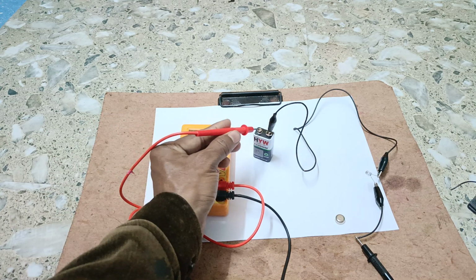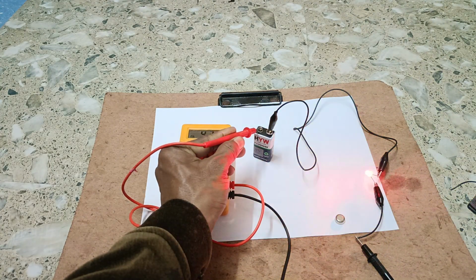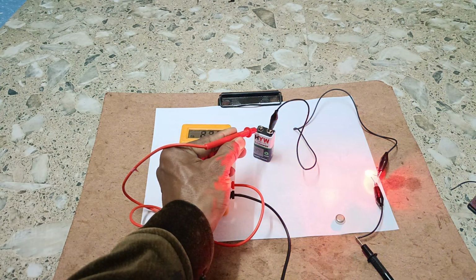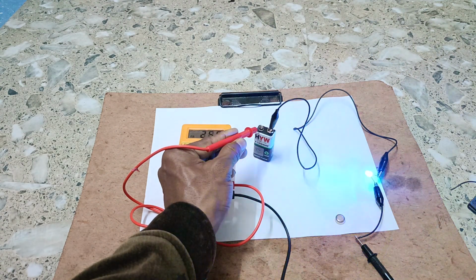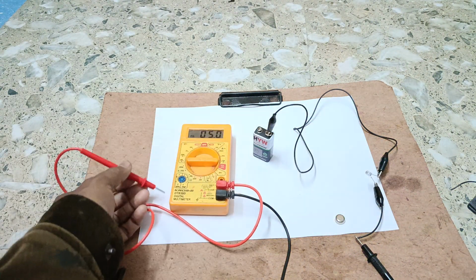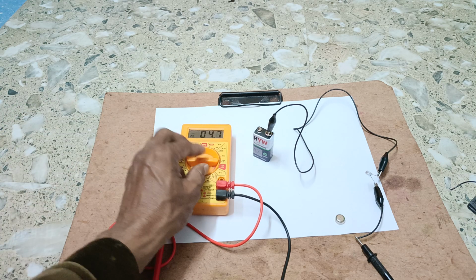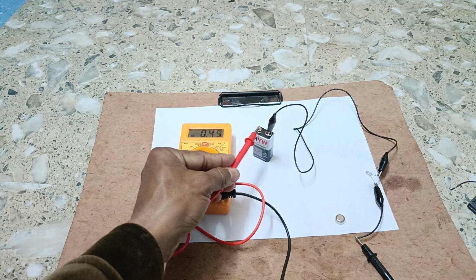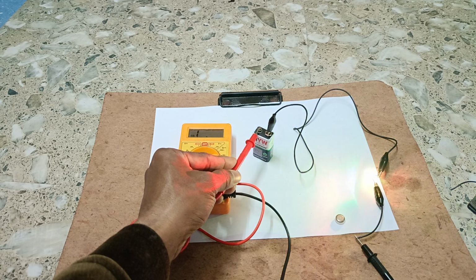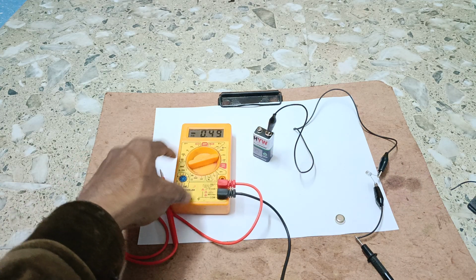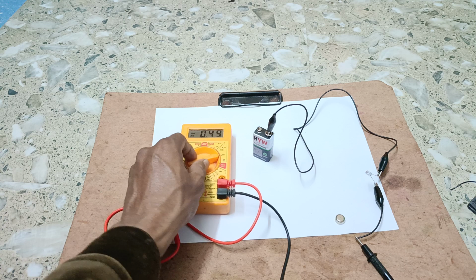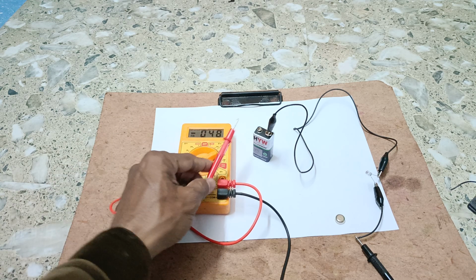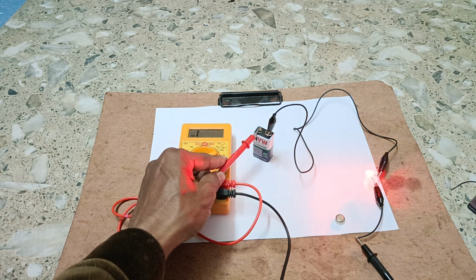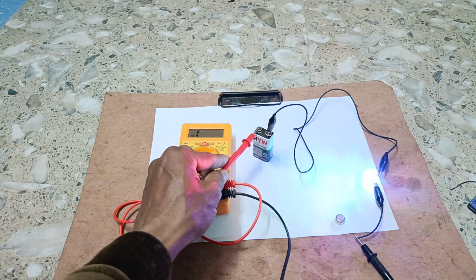Then we are putting it at 200 milliampere, and if you change it, right, it is glowing, and the current is fluctuating, but it is nearly 30 milliampere, right? And if you put this on 20 milliampere, you will not get any value. Why? Because it is exceeding 20 milliampere, right? That's why we are not getting the value, right? And if you put it at 2000 microampere, it also exceeds this limit, and it will show as 1. You see, it is showing as 1, right?